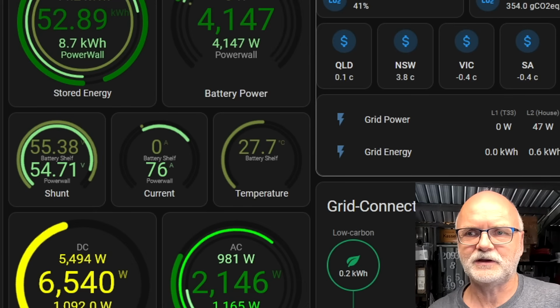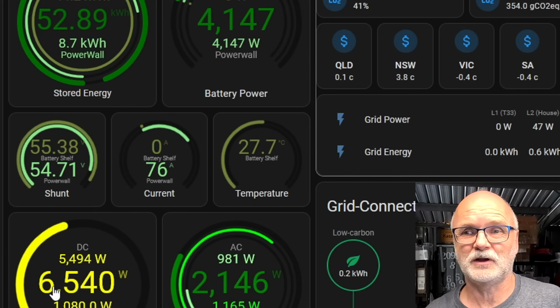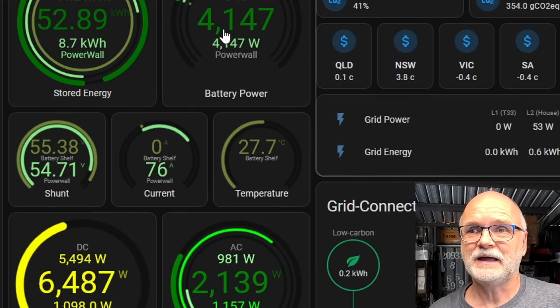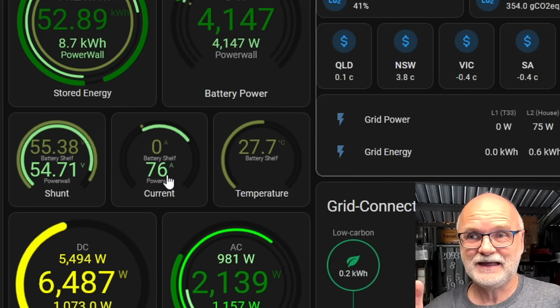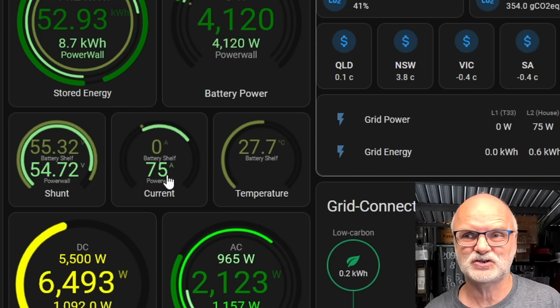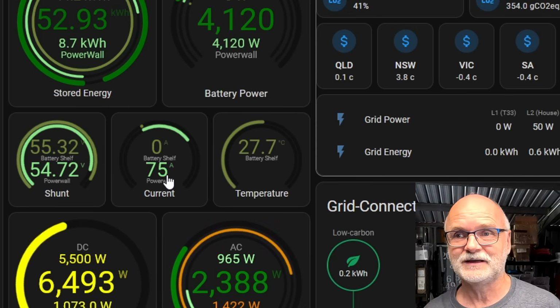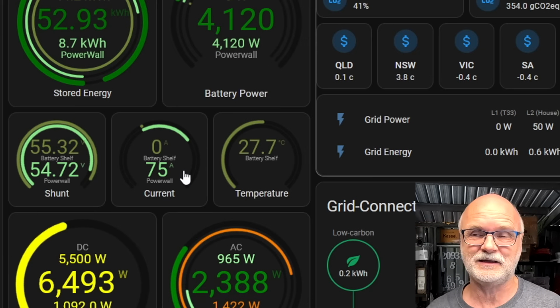All right, we can now see we are getting 6.5 kilowatts from the solar system, and we are charging the batteries now with 4.1 kilowatts, yeah, 76 amps into these batteries. And this is pretty much the maximum it will charge, even though we have set it to 100 amps. But it also reduces the charging current here for the batteries because of the DC load we have, yeah.